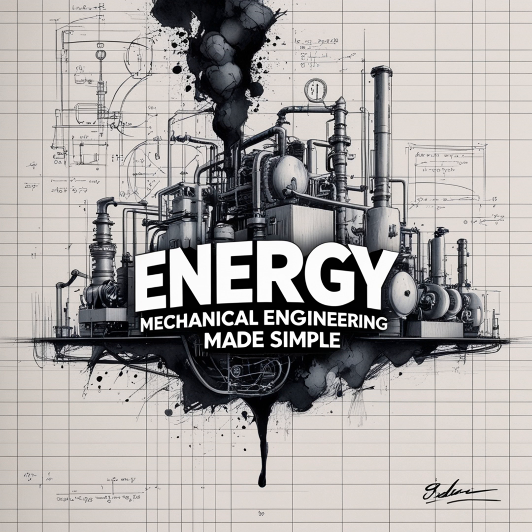That's the kicker. Power, P, is proportional to N cubed. Cubed. Wow. So even a small reduction in speed gives a huge power saving. Massive. If you reduce speed by just 20% to 0.8 N, the power drops to 0.8 cubed, which is only about 51% of the original power. Yeah. You save almost half the energy.